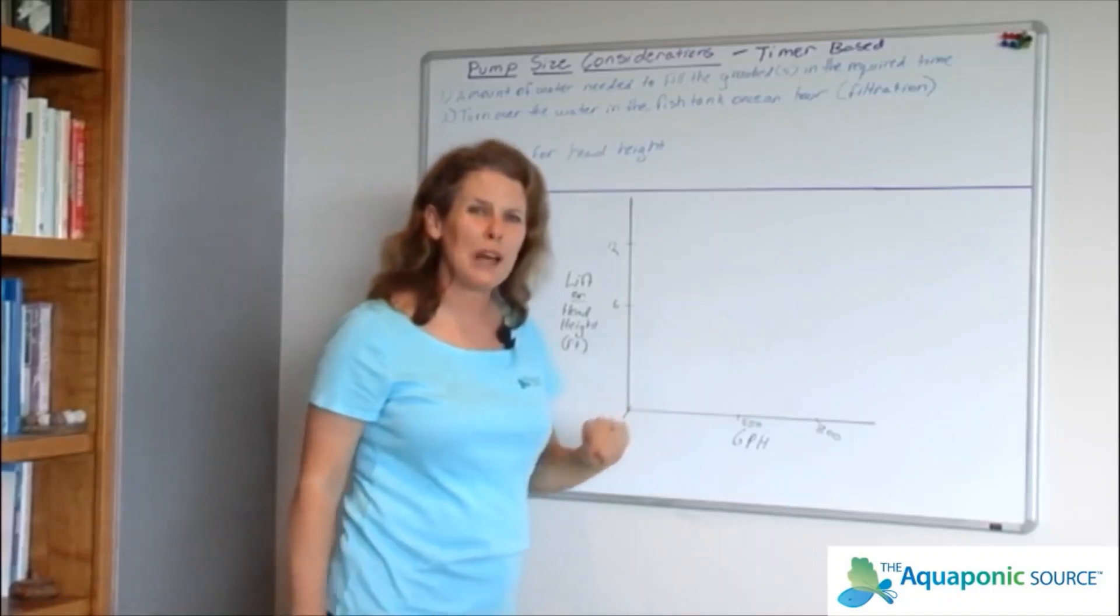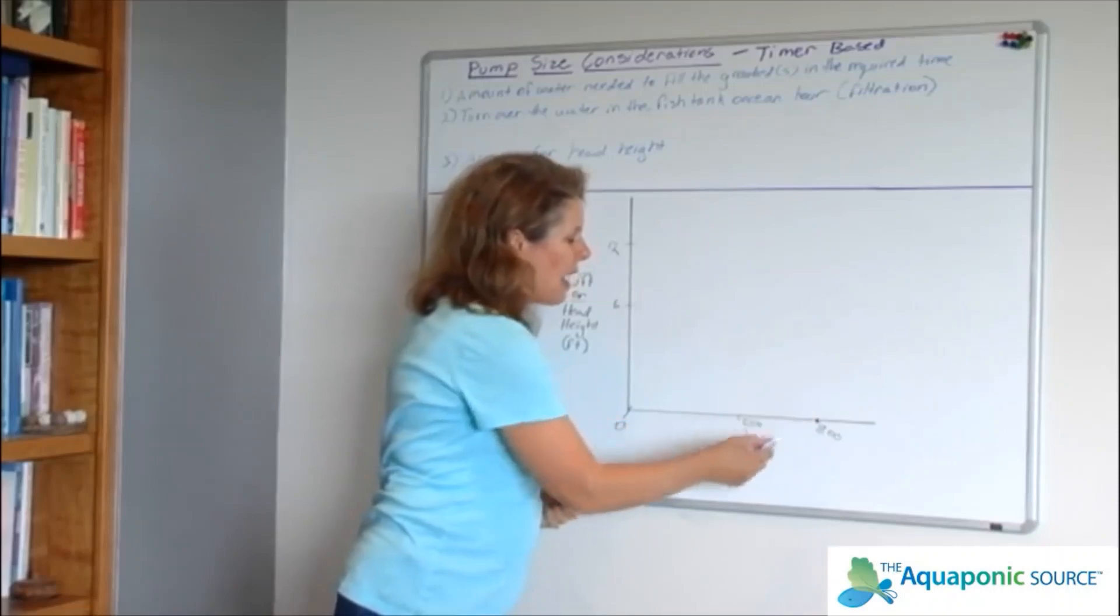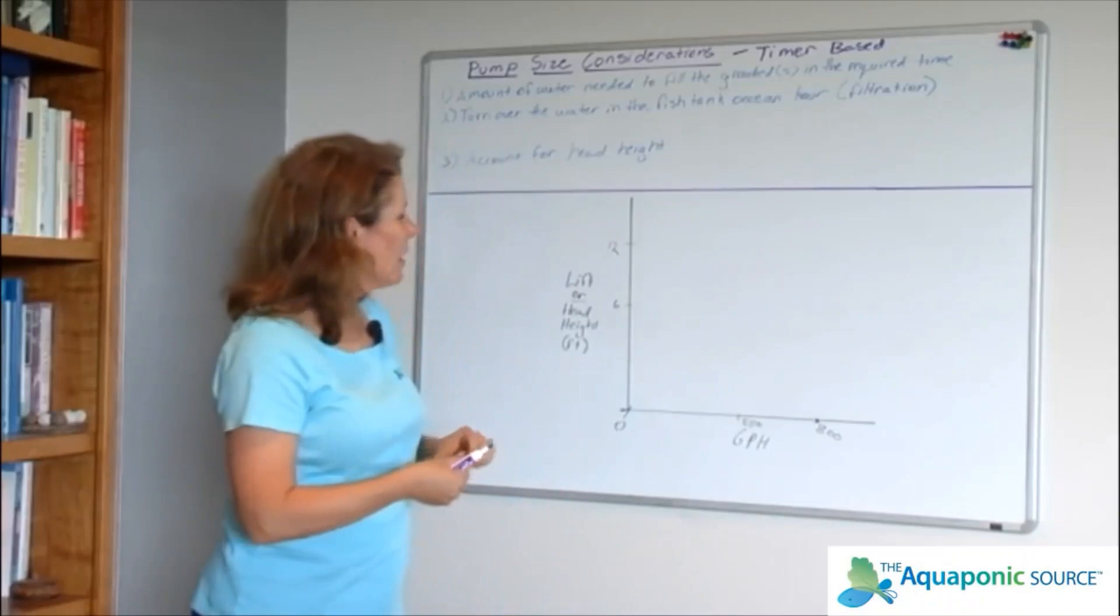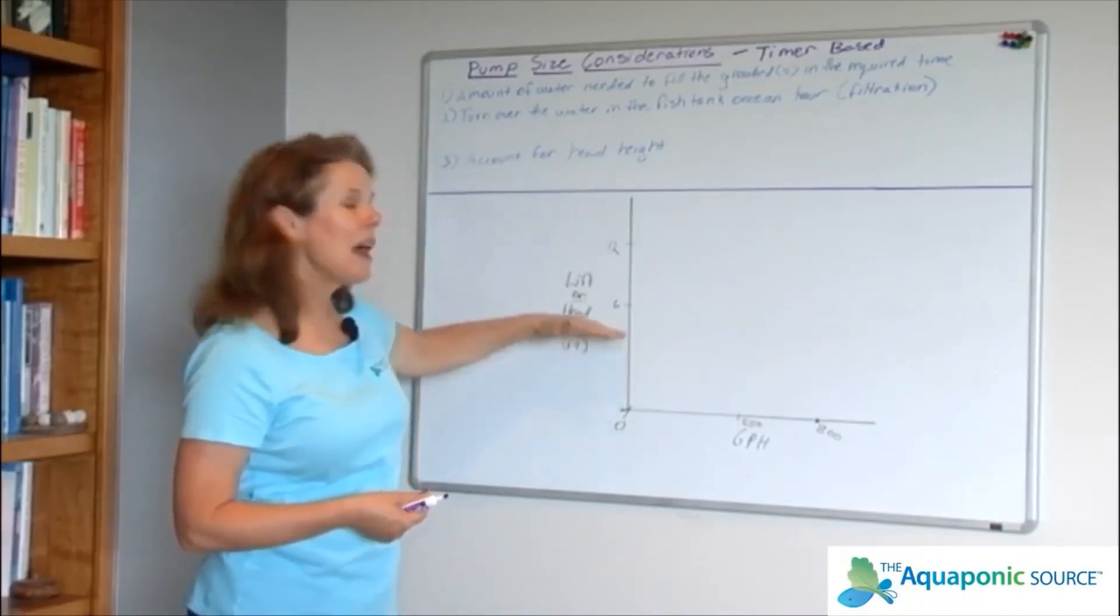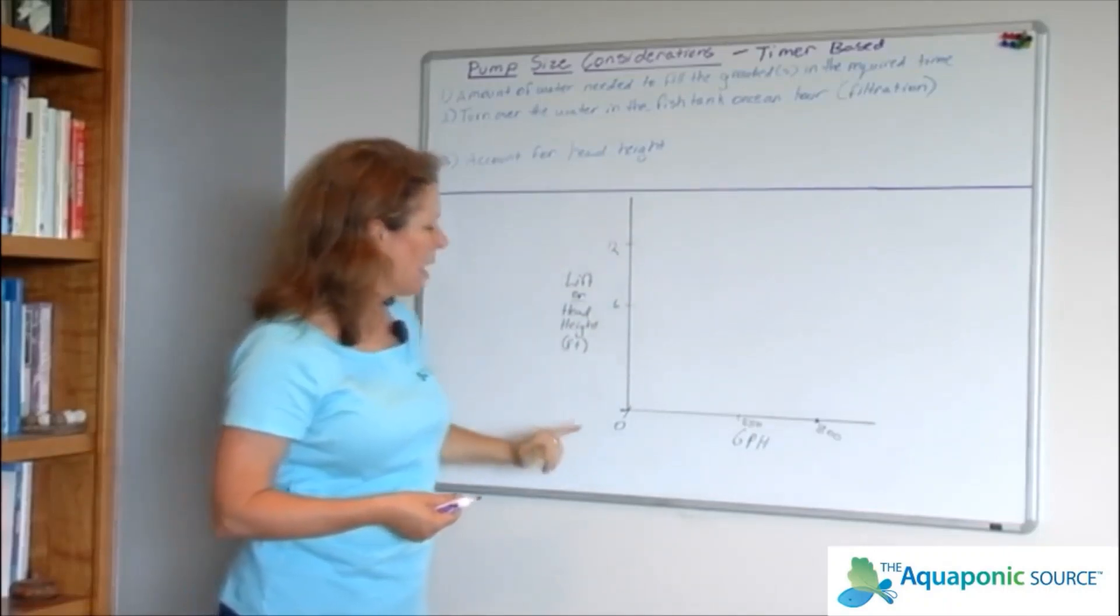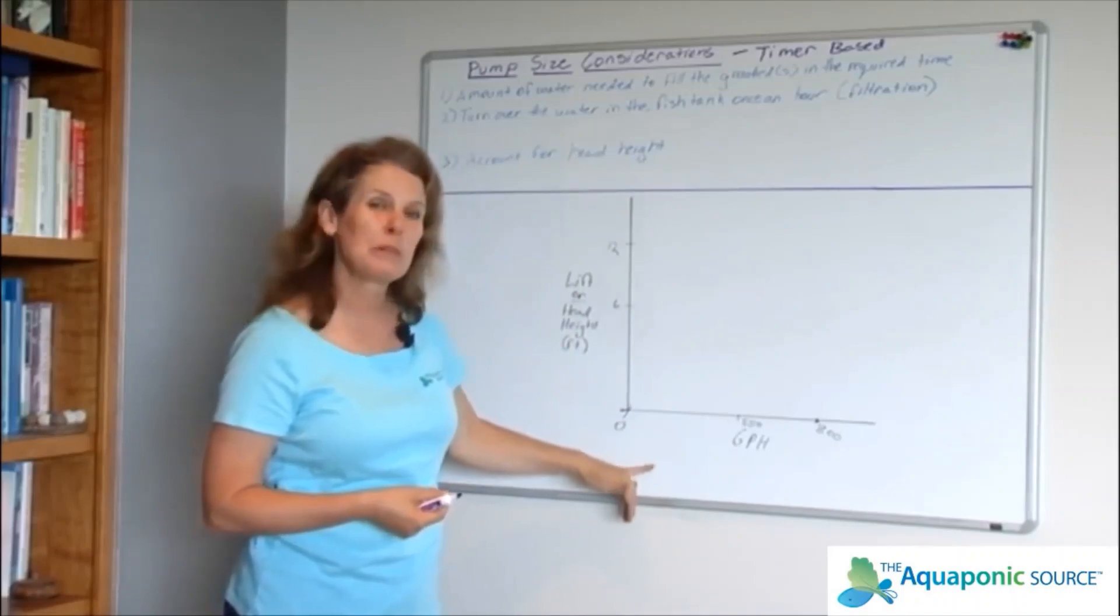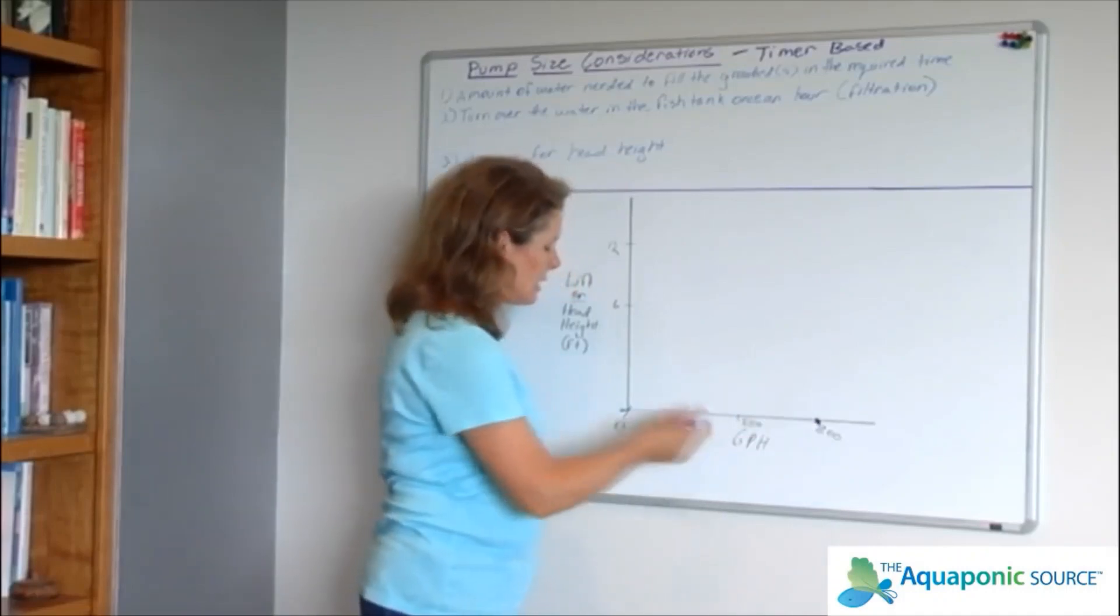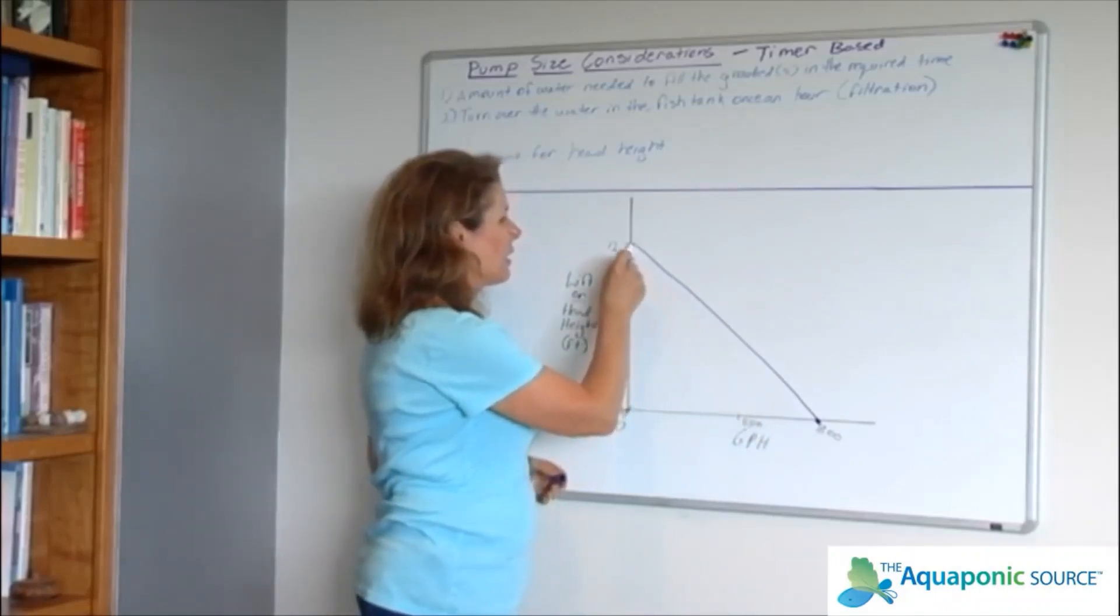Let's take an 800 gallon per hour pump, which is the purple line on the chart that you're looking at. At 800 gallons per hour, that's only at zero lift. This vertical axis here is showing in feet how high up you're trying to push that water, and this horizontal axis is showing gallons per hour or the performance of the pump.